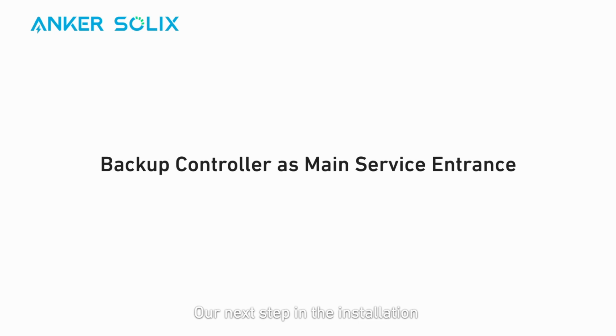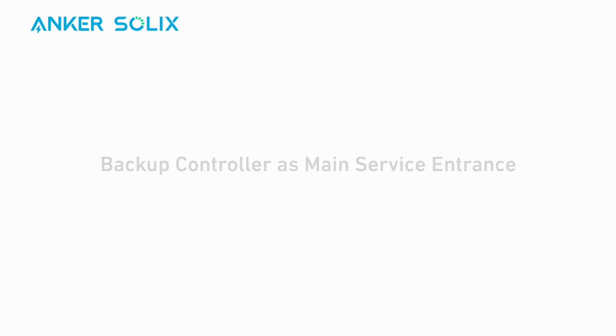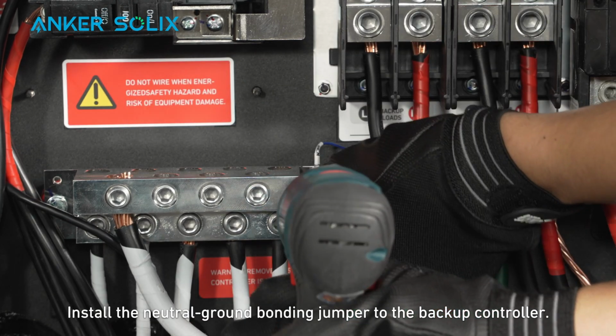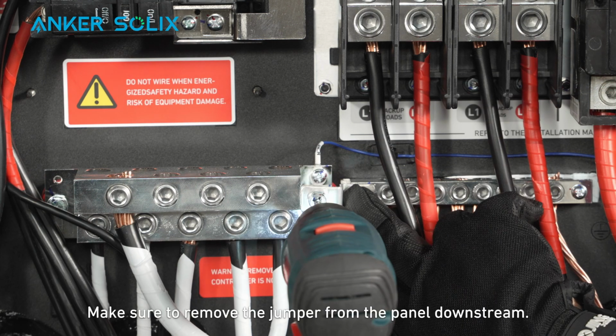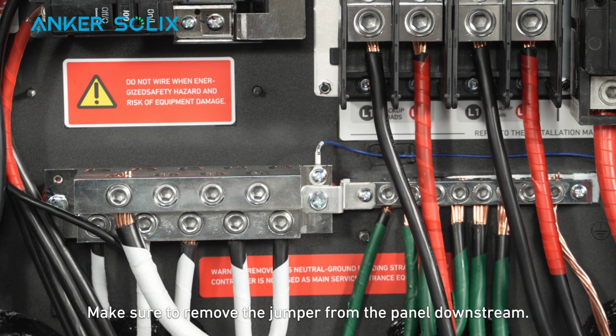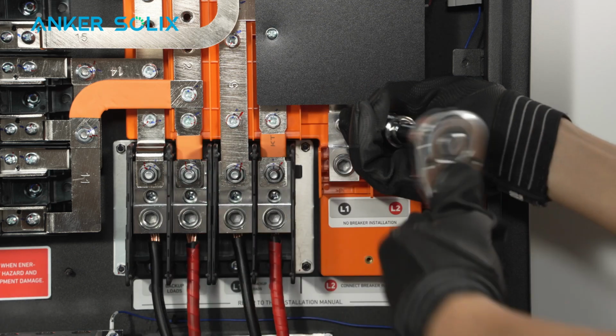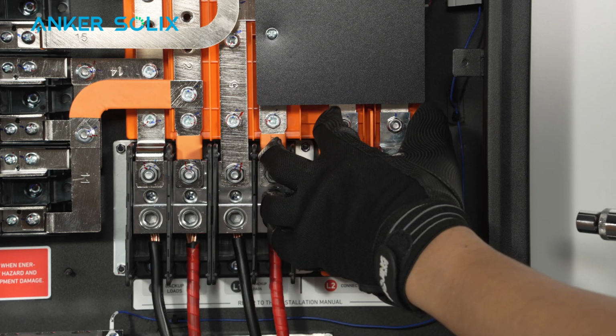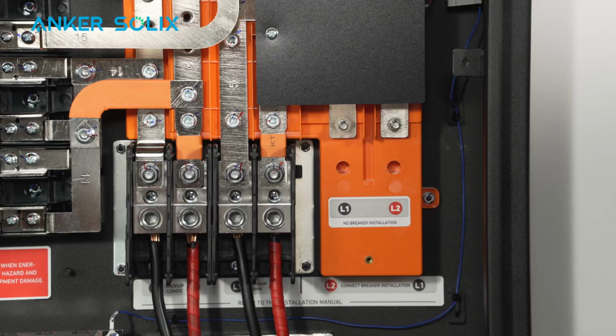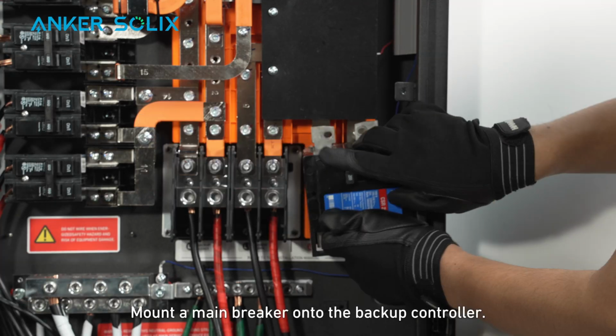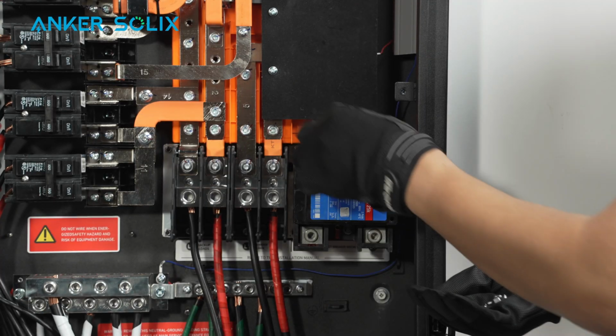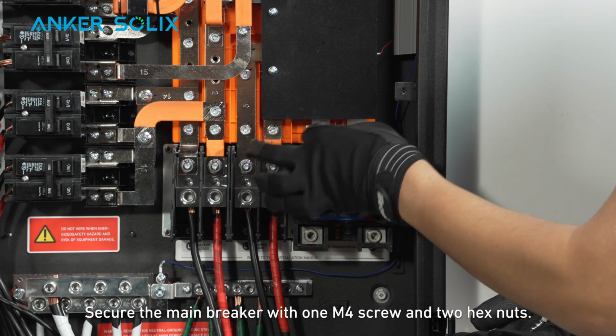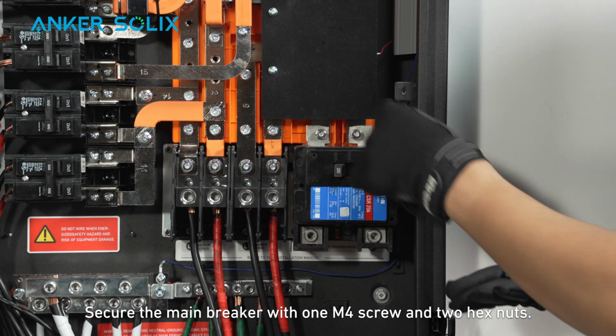Our next step in the installation depends on how you use your backup controller. If it's the main service entrance, follow these steps. Install the neutral ground bonding jumper to the backup controller. Make sure to remove the jumper from the panel downstream. Mount a main breaker onto the backup controller. Secure the main breaker with one M4 screw and 2 hex nuts.